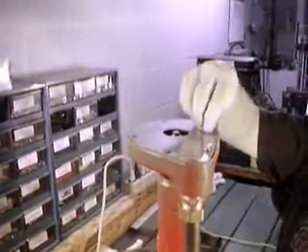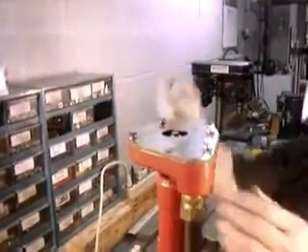Our new end plate. Now we may not always necessarily have to replace your end plate. That's something that you can probably just clean up. The gaskets are the items that you'll probably replace because of the solvents and time that they're being used. They wear out. And we snug those back up again.